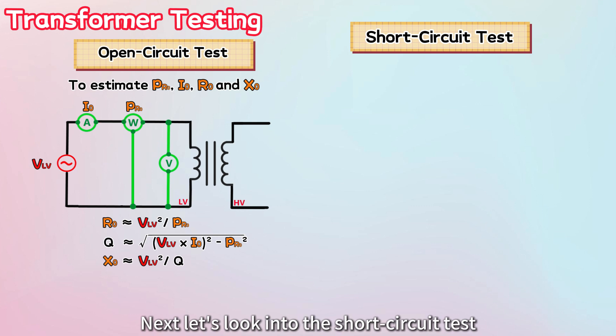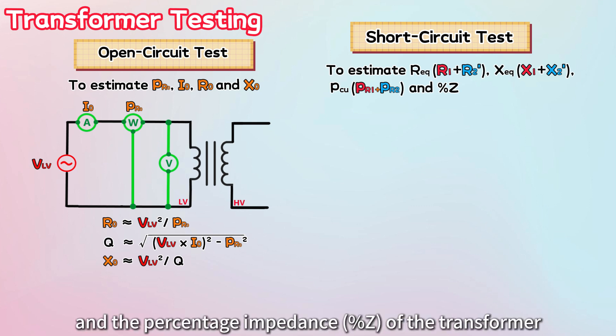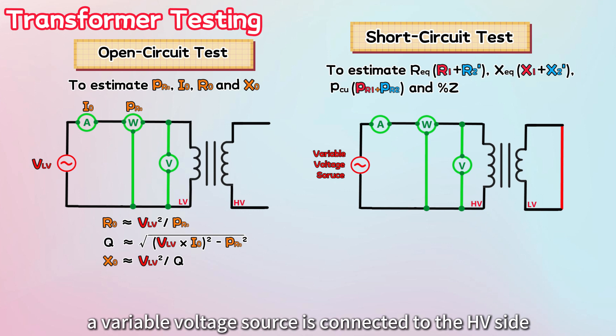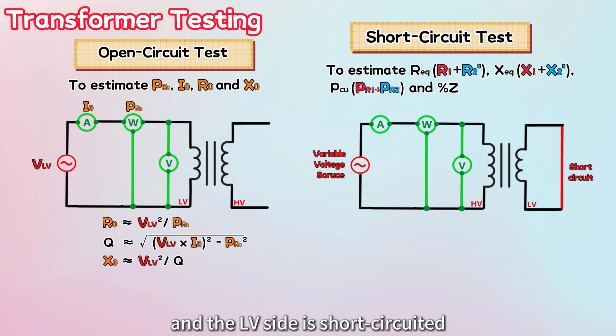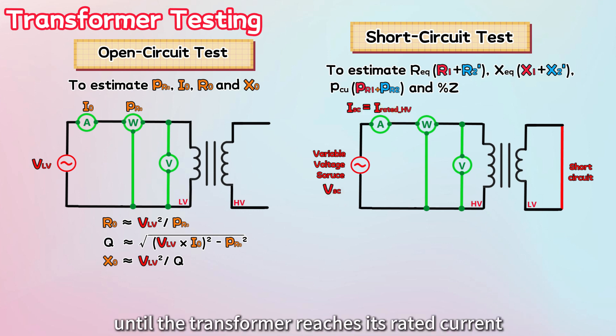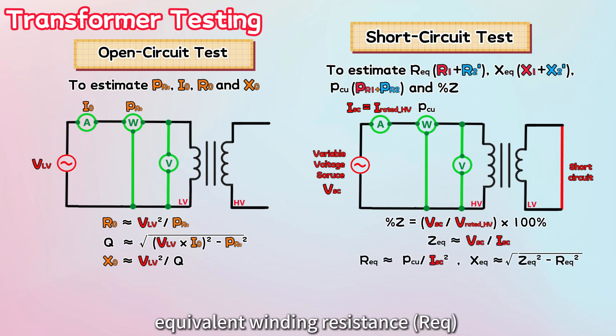Next, let's look into the short-circuit test. A short-circuit test is performed to determine the equivalent winding resistance, equivalent leakage reactance, copper loss, and the percentage impedance of the transformer. For this test, a variable voltage source is connected to the HV side, and the LV side is short-circuited. Now, we gradually increase the supply voltage from zero until the transformer reaches its rated current. The voltage required to reach this current can be used to calculate the percentage impedance, which is crucial for fault analysis. The wattmeter reading during this test corresponds to the copper loss. Subsequently, we can approximate the equivalent winding resistance and leakage reactance using the appropriate formulas.